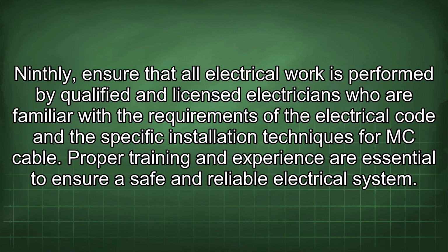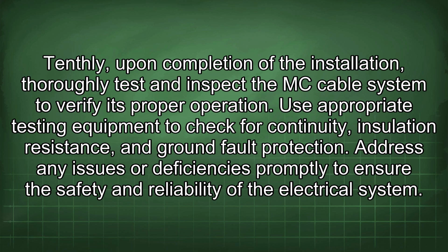Ninthly, ensure that all electrical work is performed by qualified and licensed electricians who are familiar with the requirements of the electrical code and the specific installation techniques for MC cable. Proper training and experience are essential to ensure a safe and reliable electrical system. Tenthly, upon completion of the installation, thoroughly test and inspect the MC cable system to verify its proper operation. Use appropriate testing equipment to check for continuity, insulation resistance, and ground fault protection. Address any issues or deficiencies promptly to ensure the safety and reliability of the electrical system.